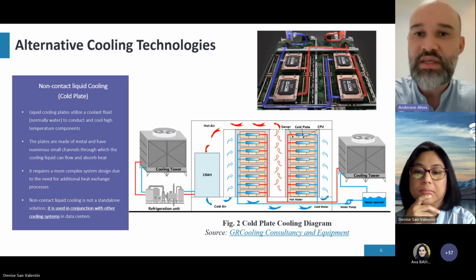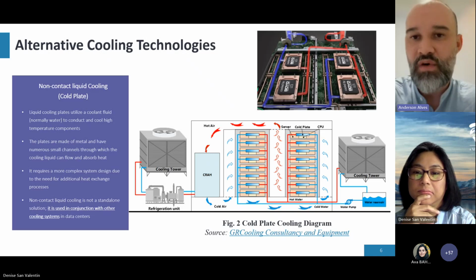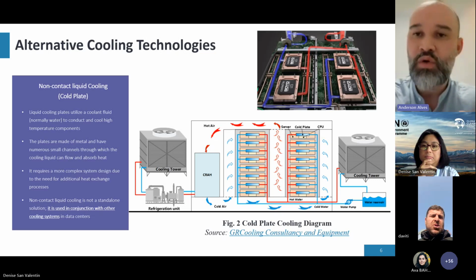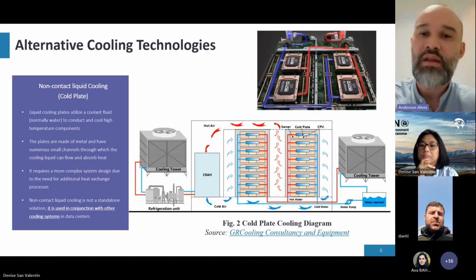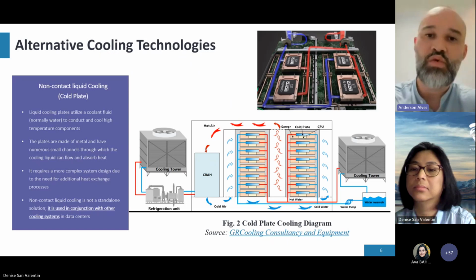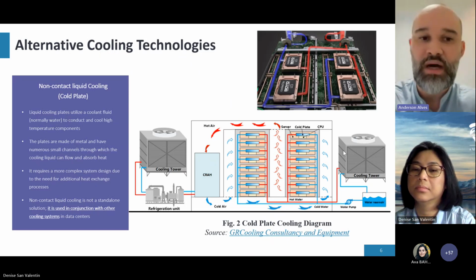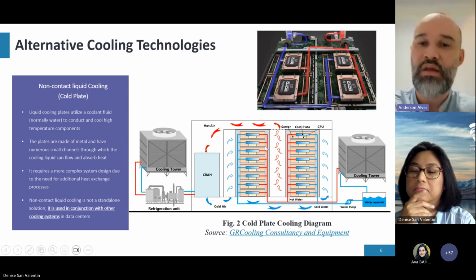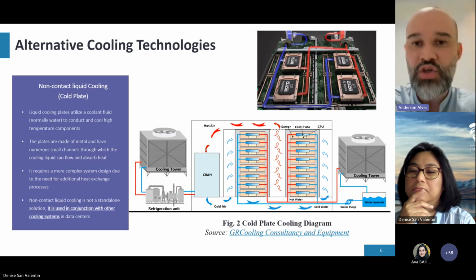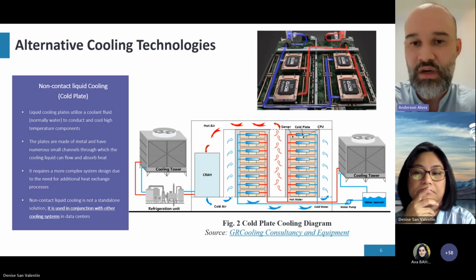Basically, you design the rack in a way that you have a cold plate in direct contact with the CPUs, for example, or the GPUs. So this water will cool the plate, and then the hot water that leaves on the other side will be recirculated by the cooling tower and comes back cool again, and this process continues and continues. But the problem here is that, as you can see from the diagram, you still need a refrigeration unit to remove the residual heat, the air that is in the system, right?